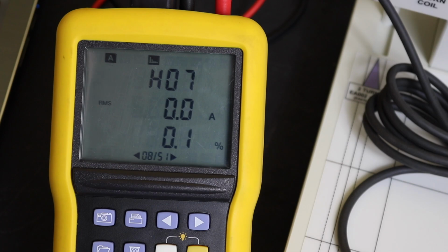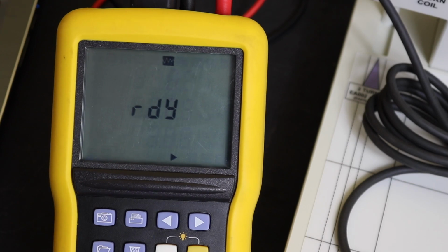Our next function we need to go to is our startup, which I will need to change the program on the injection test set, so just bear with me whilst I do that, and we can have a look to see how well that works. Okay, so we've set up our program. Our Inrush program is set to supply 80 amps Inrush over 115 milliseconds.